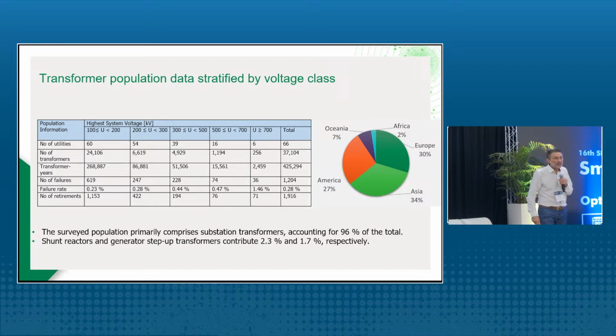Most of these transformers are substation transformers, or you can even call them grid coupling transformers, not generator step-up units. A generator step-up unit is located in a power station, and normally such a unit is more heavily loaded than a substation transformer. The grid coupling transformers normally have a lower load during operation, and the effect is of course that the aging of these substation transformers is also less. So the data I'm now presenting is 96% based on substation transformers.